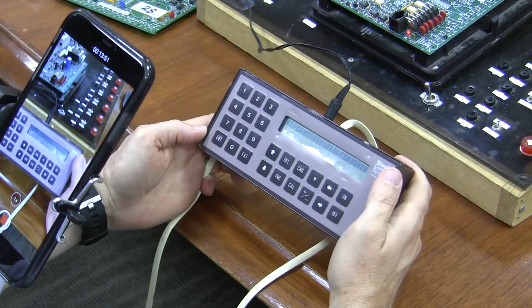And I'm going to go to commissioning mode because if I power down and power back up like I just did, I'm not in commissioning mode anymore. So I'm going to go function, enter on set servicing mode. I scroll up to commissioning mode and then I hit enter. And now I'm back here at input. And if I look here, I'm looking at the zone temperature, but in the little left corner here, it isn't a CH, it's a CL. And CL means that I could calibrate it.